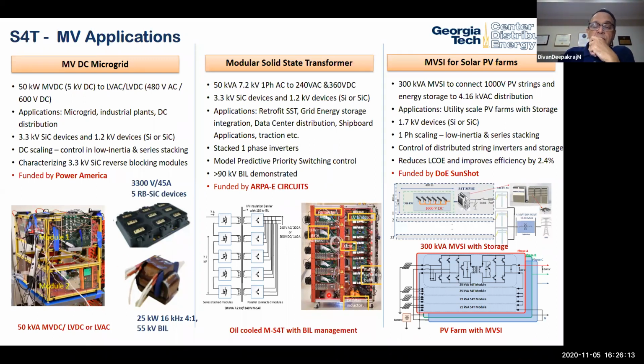We've also been working through an ARPA-E project to build a 13 kV class — 7.2 kV phase-to-neutral voltage — 50 kW solid state transformer with DC and AC output on the other side. A very challenging project, because getting these stacked, low inertia devices to work together was very difficult. But more important than that — everybody's been talking about these devices replacing transformers, and the fundamental problem is that the transformer isolates us from things like lightning strikes on the AC line.